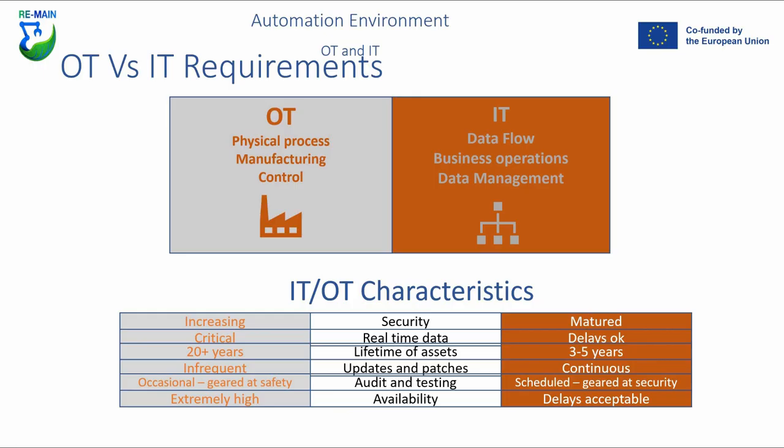Real-time data is a critical aspect of operational technology. Within IT, delays are expected and acceptable, but this would not be okay in an OT environment where response times for control decisions may need to be within 20, 30, or 40 milliseconds. Real-time data is critical for OT but not so critical for the IT environment.